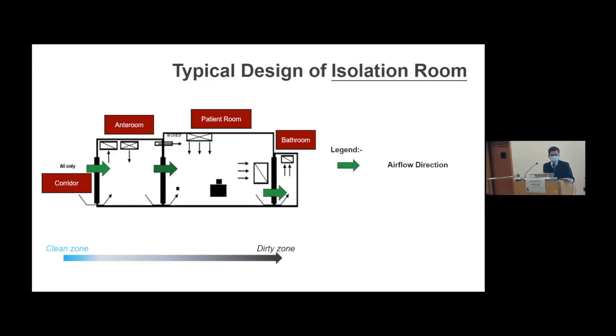Exhaust fans are installed inside the patient room and bathroom. The designed airflow direction of a negative pressure isolation ward is from corridor to anteroom to patient rooms and bathroom. The air then passes through a filter and is extracted to outdoor. In order to achieve the desired airflow direction, we need to create a negative pressure environment by having fans which extract air at a higher flow rate than that of the supply air.